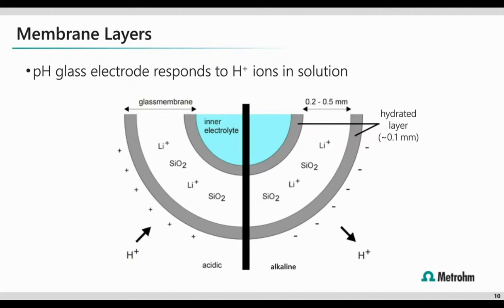So when the electrode comes into contact with a sample solution, H+ ions are either diffused into or out of the gel layer, leaving behind a charge. So think, for example, just maybe on the right-hand side, we're looking at an alkaline example. So in that solution, the H+ ions diffuse out of the gel layer and a negative charge is left on the outer side layer of the gel, that hydration layer. Since the glass electrode has an internal buffer and that has a constant pH value, the potential at the inner surface of the membrane remains constant during the measurement. So bringing it full circle, we're able to get the total membrane potential as a result of the difference between the inner and the outer charges.